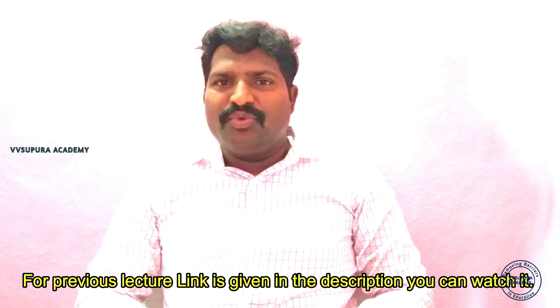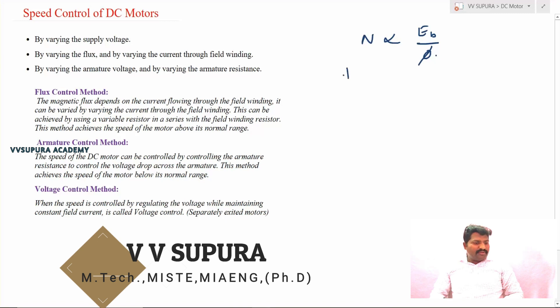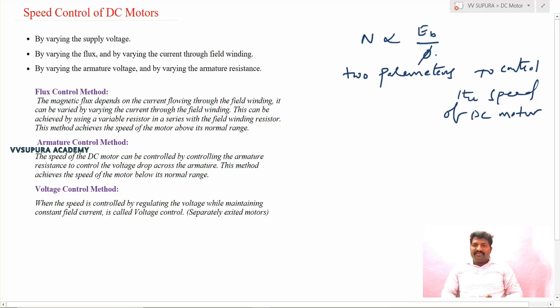In this class, let's discuss the speed control methods of a DC motor. As discussed in previous classes, the speed of a DC motor depends on back EMF and field flux. We can write the speed equation as n is directly proportional to Eb/φ. From this equation, there are two parameters to control the speed: back EMF and flux.